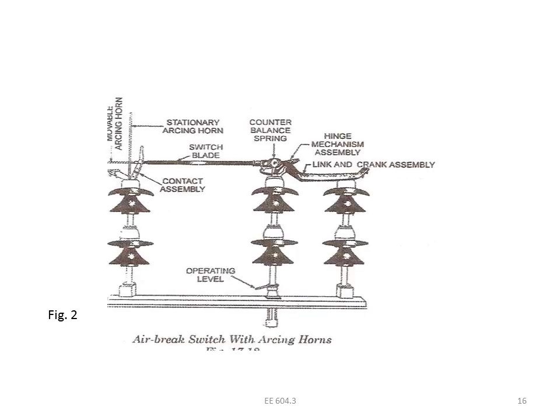Okay, this is the one type, which will be mounted at the top of the line. You can see the arcing horns. The arcing horns remove the arc between the lines whenever the switch is opened. So the arcing horn removes the arc between the lines when it is disconnecting the lines.